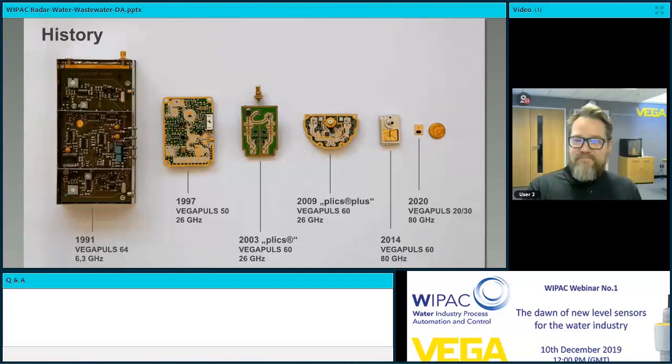Radar technology was already being used for level measurement at that time. When we looked at it, we could see that it was being used on massive oil storage tanks with a millpond surface, a big transmitter, and a ticket price and complexity to match. But that was okay because it was accurate to the millimeter in fiscal, tax-regulated applications. So it met the criteria, and we could see that the basic technique was viable. Components became more available, so our work on a process version of these radar level transmitters began.